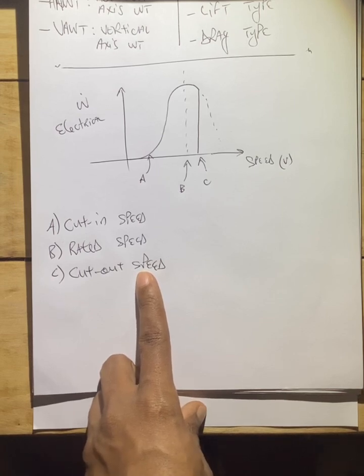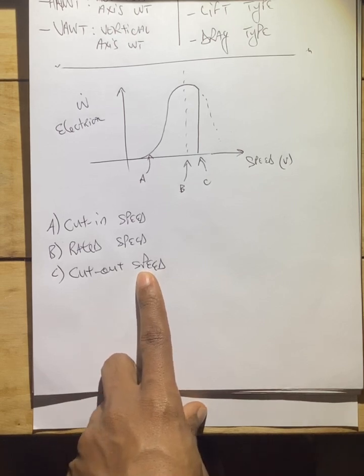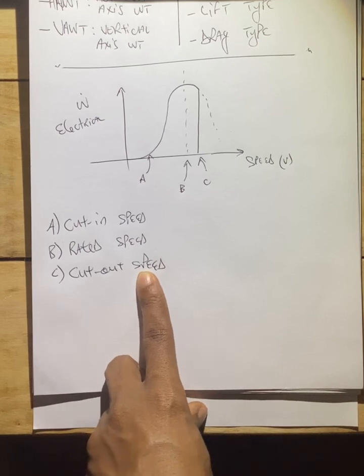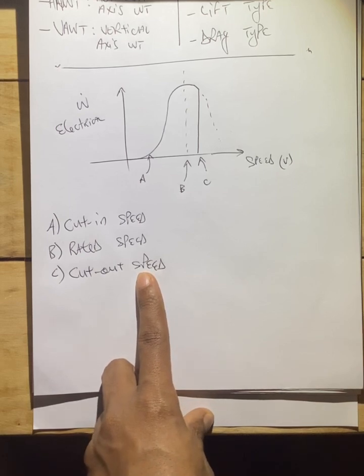So simply meaning the moment the speed goes above and beyond rated speed, it's in dangerous territory. It's still going to generate power, but the objective at that point is not to generate power. The danger is that you are now operating outside the design specifications. So for that, we now need to apply braking so that the speed can be reduced to a point where it's either rated speed or below.